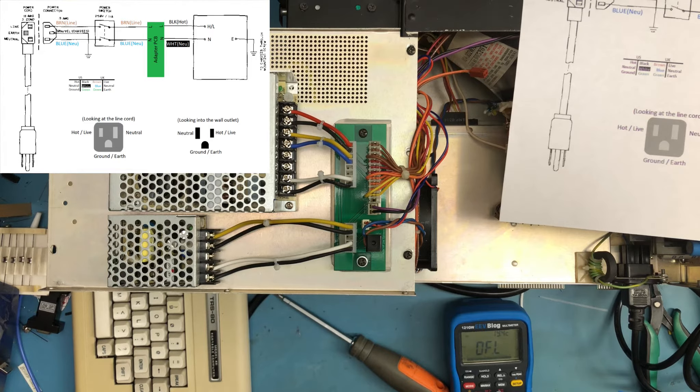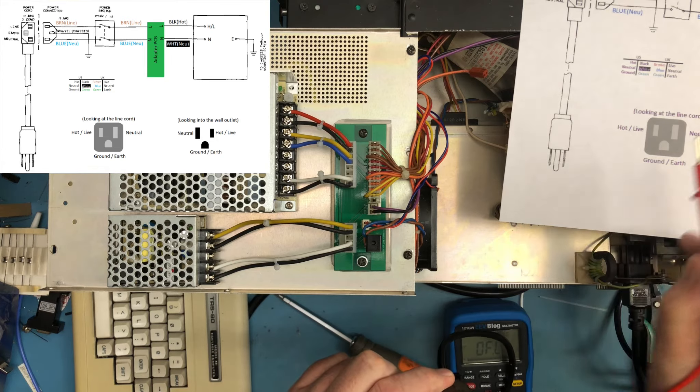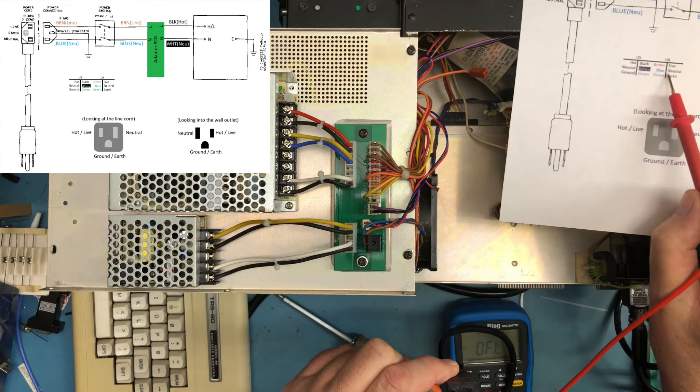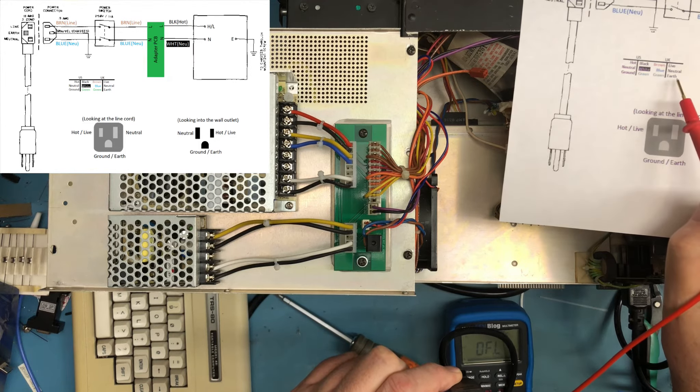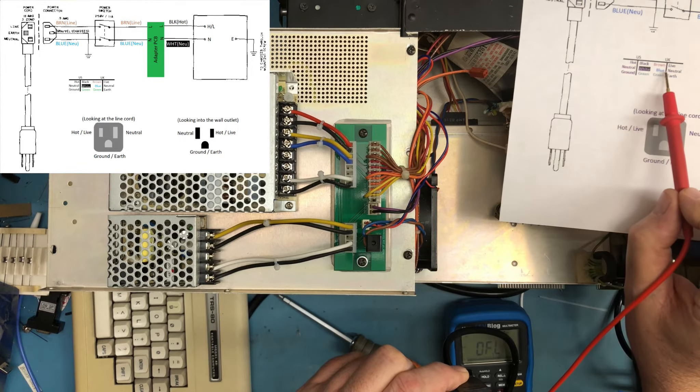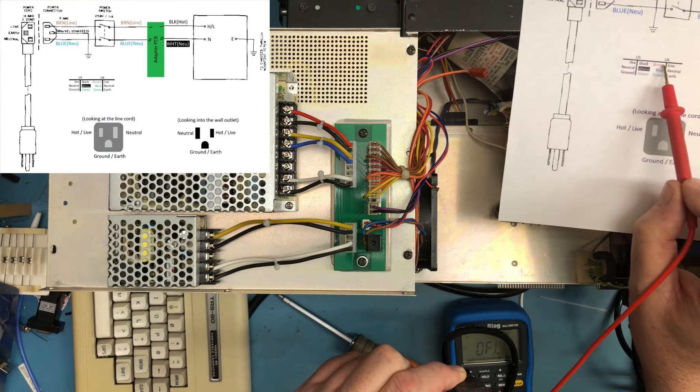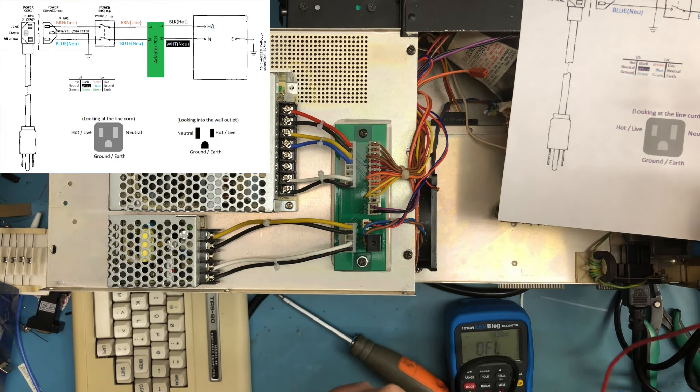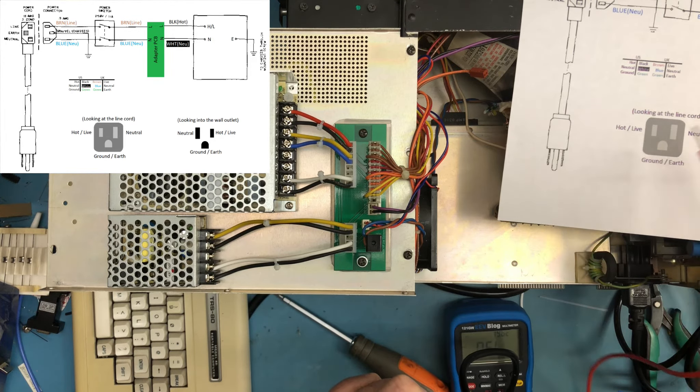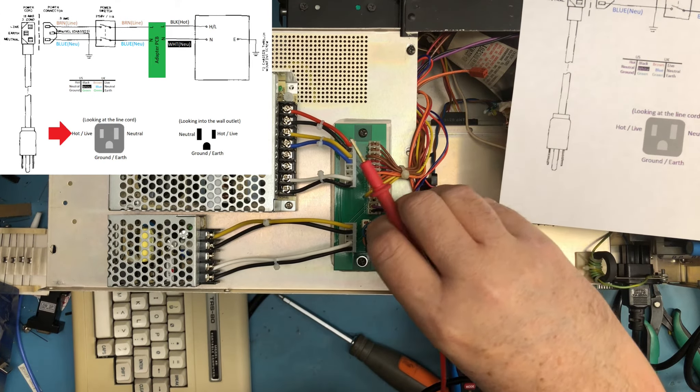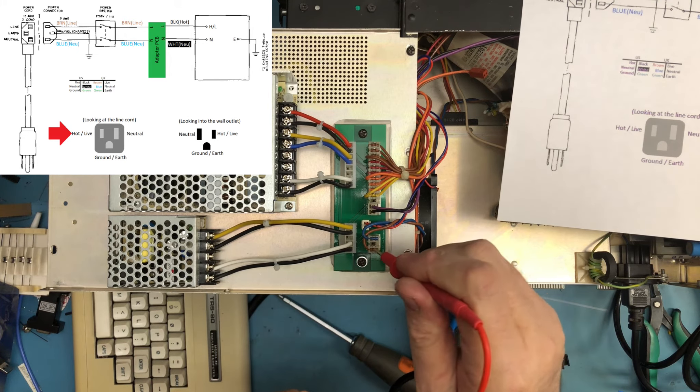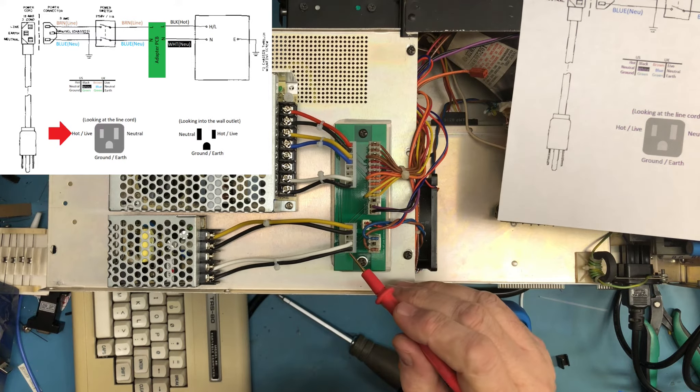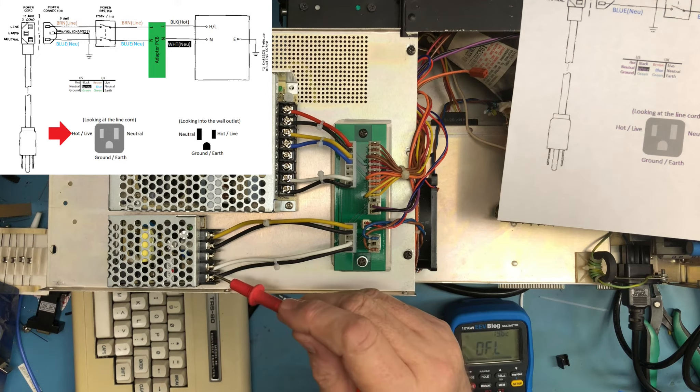So let's look at this. I'm going to get on the live, the hot or live. There's a chart here. It's got US and UK. In the US it's hot, neutral, and ground. In the UK it's live or line, neutral, and earth. Basically green to green says that's equivalent. It's blue in the UK, it's white in the US. It's brown in the UK and it's black in the US. So on this side I should be a hot or live, that should be coming up to the brown wire. Let me take this little cover off here again. And we should see that all the way through to the brown wire, and we do. And that should come to the black wire. And the power supply indicates line, it's got an L right here and there's an L right here to this one. So that's correct.